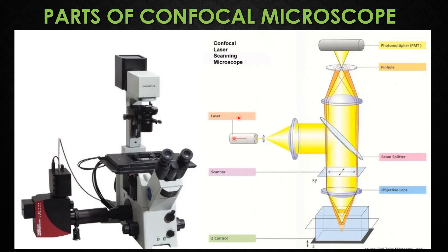The scanning system is responsible for moving the laser beam over the sample in a raster pattern, which produces an image. It is typically based on a galvanometer or acousto-optic modulator. The beam splitter separates the excitation light from the emitted light in the fluorescence beam, and is a major part of the microscope.